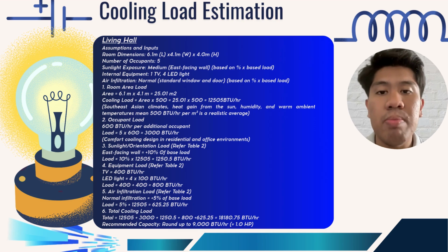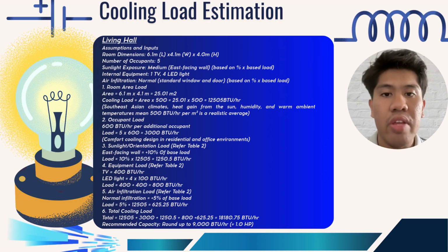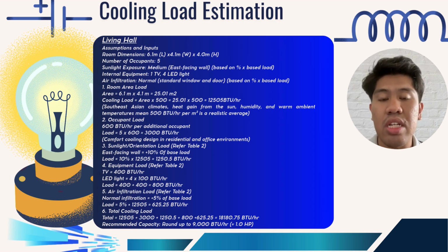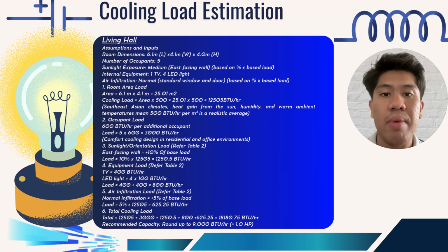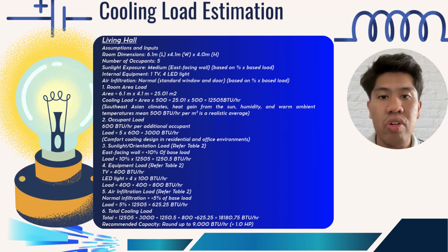Next, we go to our part, the cooling load estimation for the living hall. It is performed to determine the appropriate air condition capacity needed to maintain thermal comfort. This calculation considers several factors that contribute to heat gain within the rooms, which must be offset by the air conditioning system. So the first thing is find the room area load.